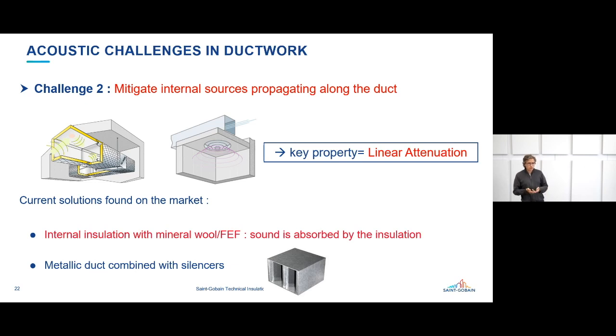So basically what we are doing with this first solution is absorbing the sound in the insulation material. The sound is propagating inside the duct, but thanks to the insulation, we are able to dissipate the sound from the source to the opening of the duct. The second very common solution we can mention is the metallic silencer, which can be combined at some point of the ductwork to provide some good linear attenuation property.